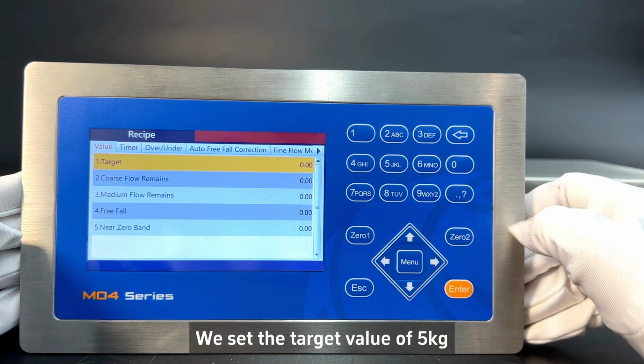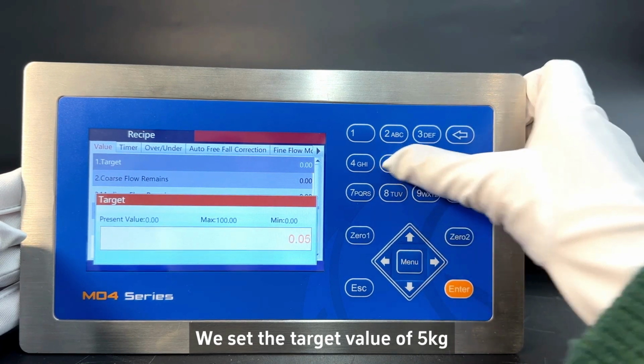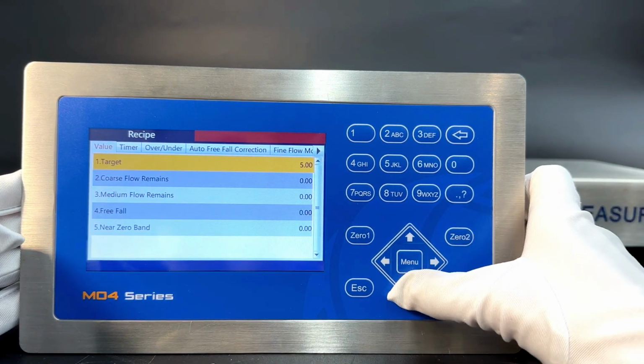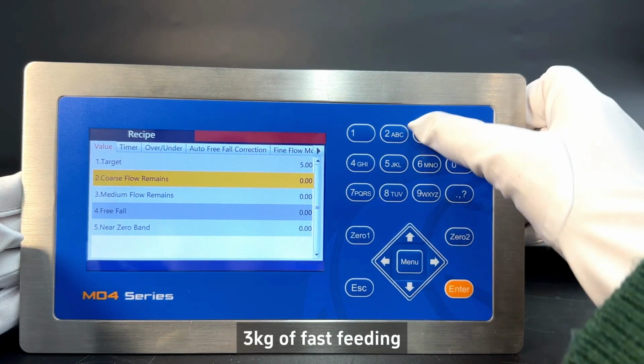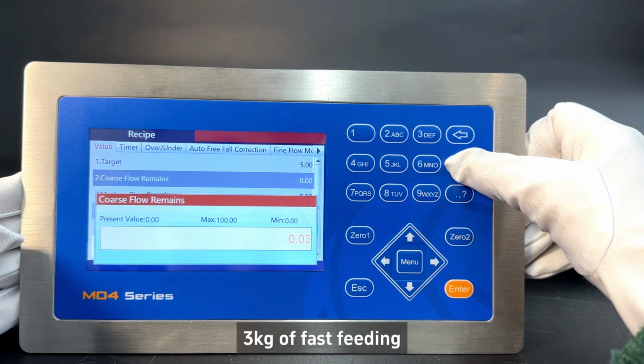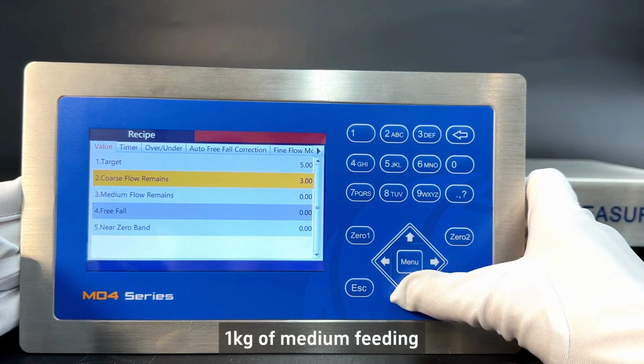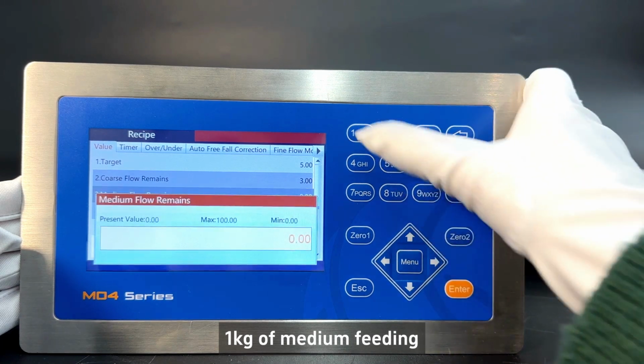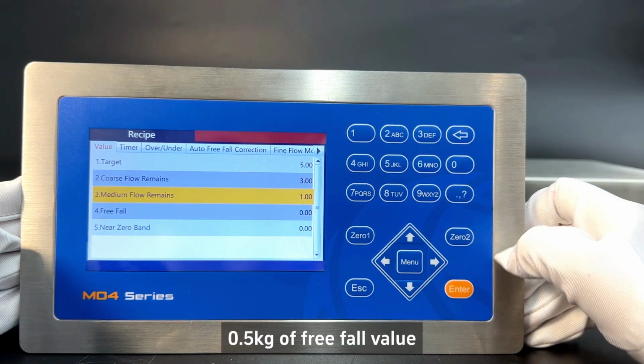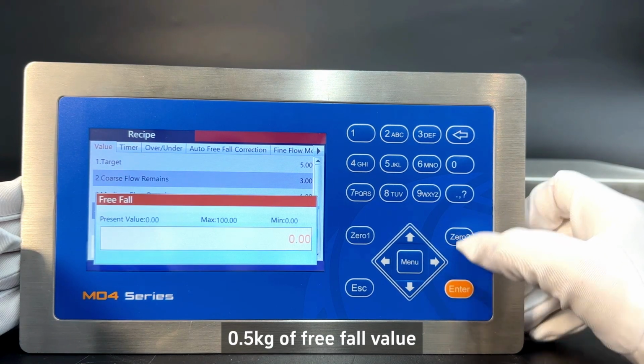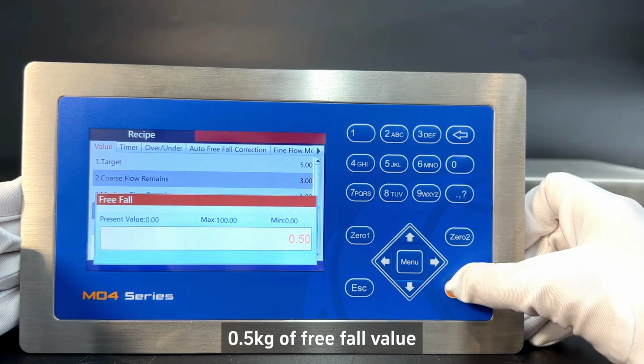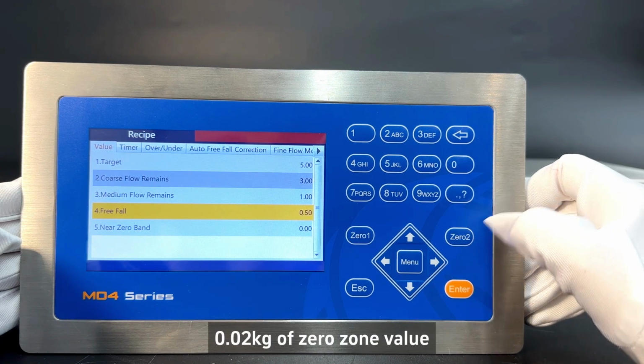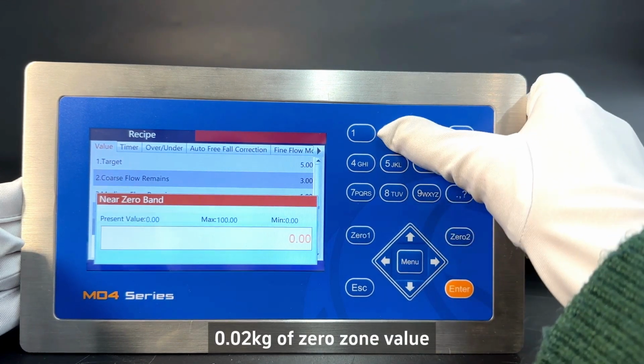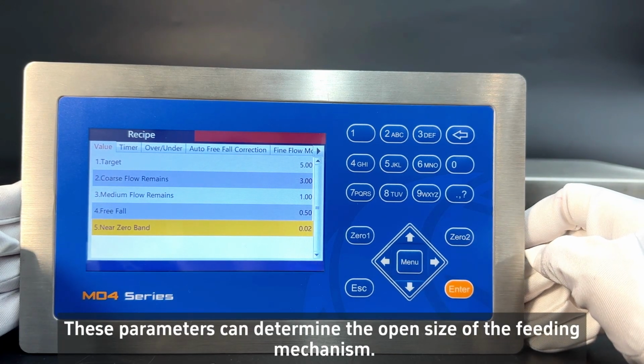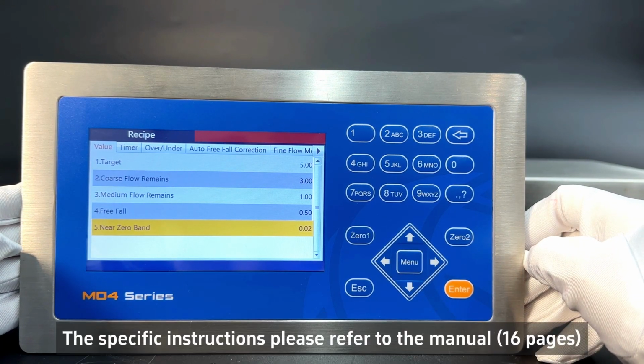We set the target value of 5 kg. Three kg of fast feeding. 1 kg of medium feeding. 0.5 kg of freefall value. 0.02 kg of zero zone value. These parameters can determine the open size of the feeding mechanism. The specific instructions please refer to the manual.